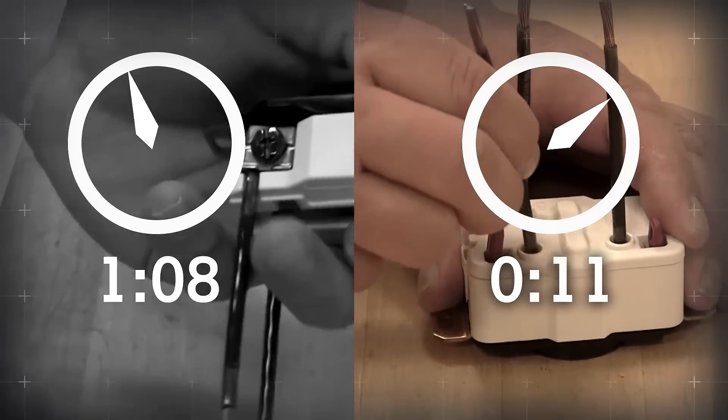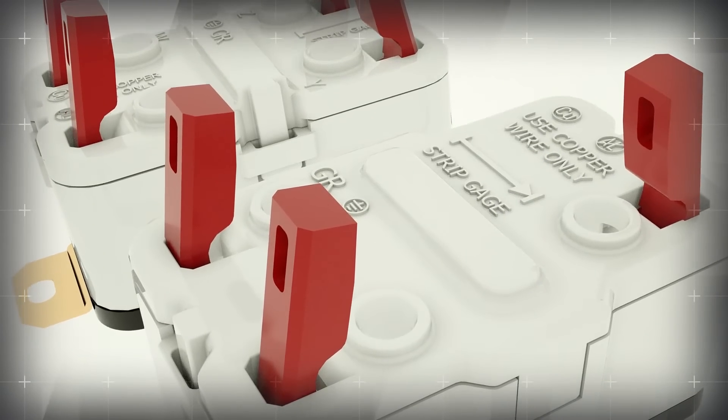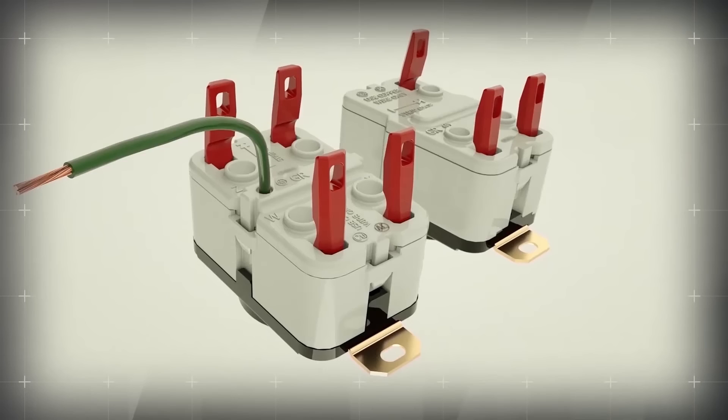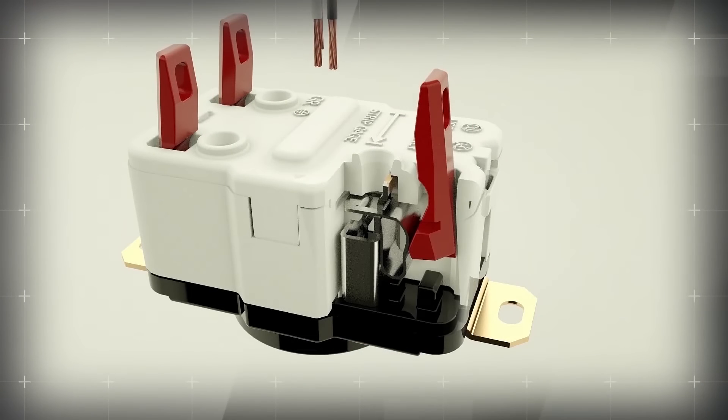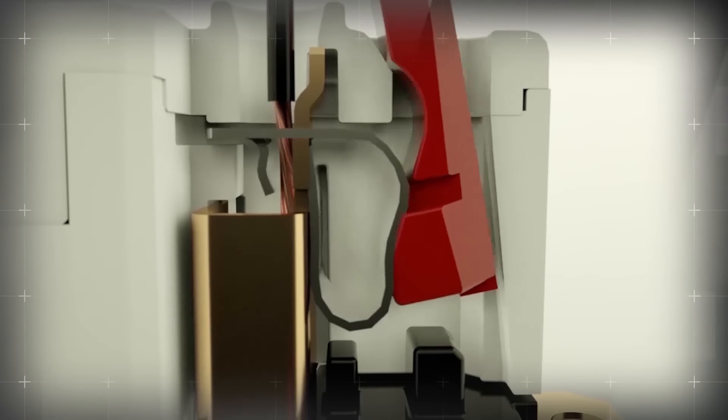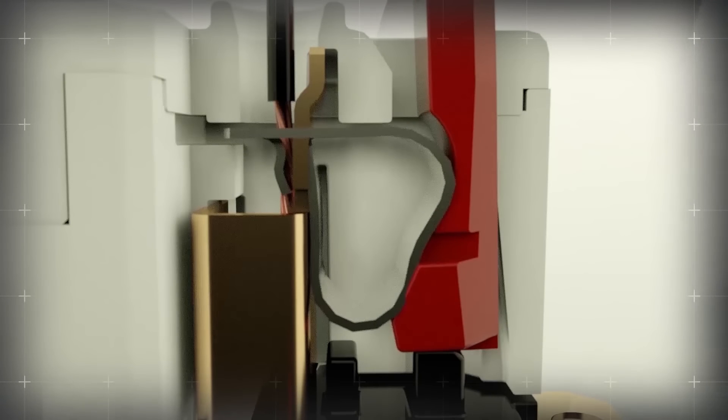So how does it work? Let's take a look at a single phase receptacle installation. Each unit's red plungers are shipped in the up position for even greater installation speed. Simply insert each wire into its adjacent compartment.